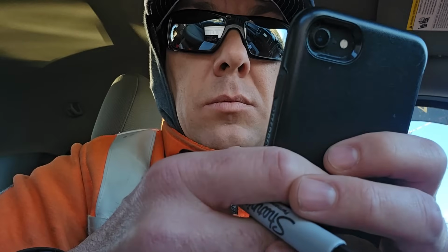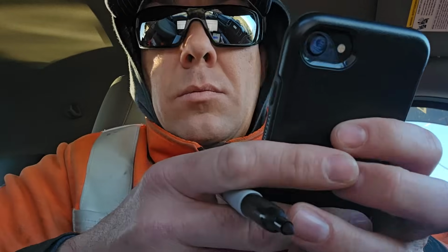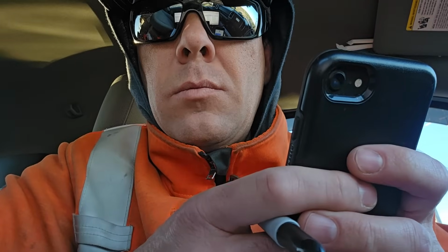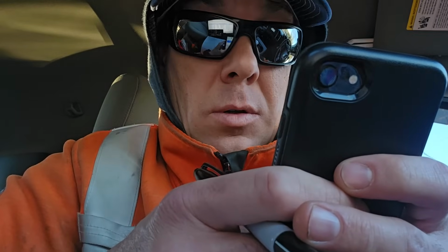10-4. Are you seeing anything else tying into my work zone there? I'll check here, Aaron. Oh, I see the normal open out there on the single phase a little ways. And then coming back, there's not a thing until we get back here to that 8209 SO10. Perfect, that's easy enough. All right, so I'll make you up a permit between those 2 protection points, that 8209 SO46 and 8209 SO10, Aaron.